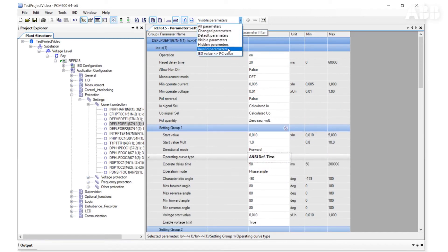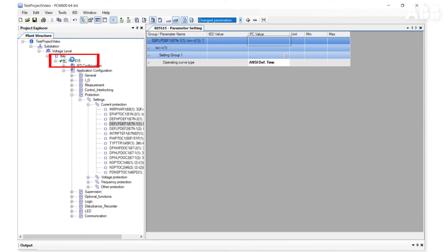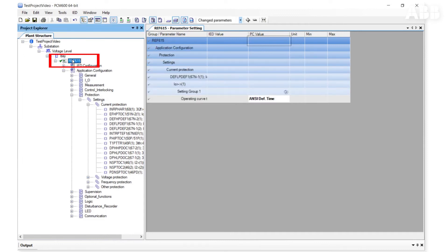If the filter Changed Parameters is selected, the tool only shows the changed parameters during the current session. If you want to see all the changed parameters for all the functions in the relay, select the relay in the plant structure and you will see all the parameters which have been changed.